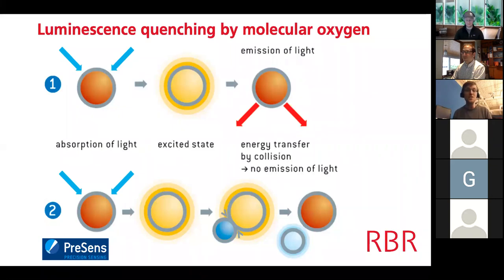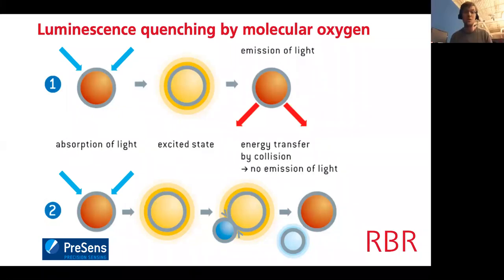Okay. All right, so I decided I would start with not just the technology behind the RBRcoda T.ODO, but the principle of measurement employed in all optodes. And this is the luminescence quenching reaction by molecular oxygen. So the main element in the sensor is a luminophore, shown here in red, which is embedded in a plastic foil or bonded directly to the glass face of the sensor.